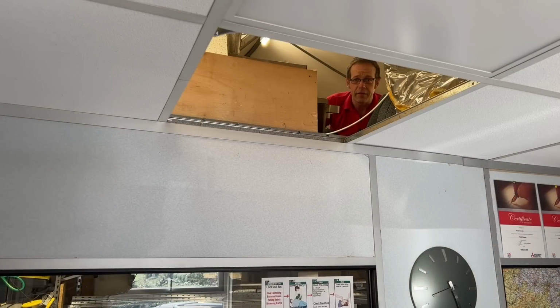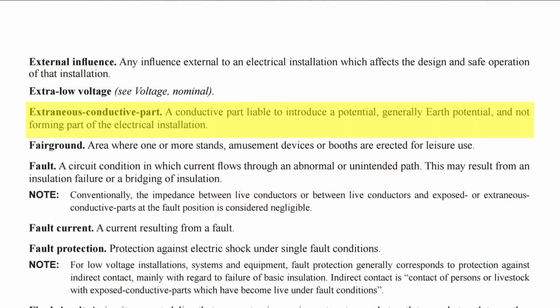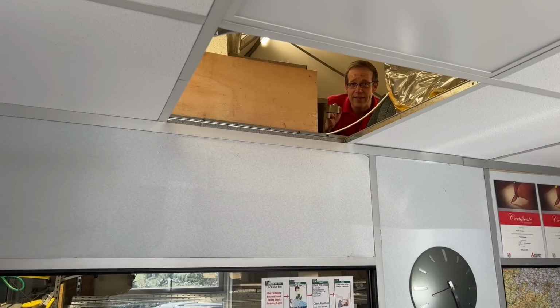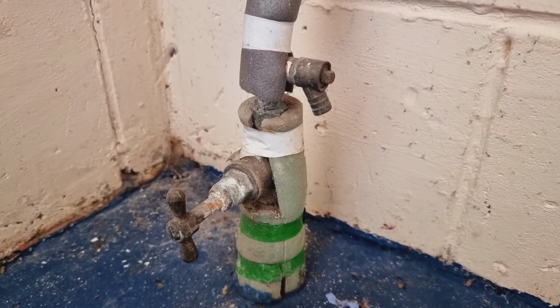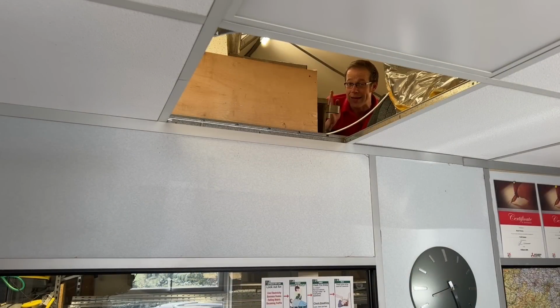And the definition of an extraneous conductive part is a part liable to introduce a potential, generally earth potential, and not forming part of the electrical installation. So again, think of this as being something extra to or outside the electrical installation and which could give a good connection to the literal earth that we walk around on. This could include metal pipes for water or gas or oil, as long as it does in fact introduce an earth potential. Again, check out the video we've made showing why you may not need to bond as many pipes as you think you do.